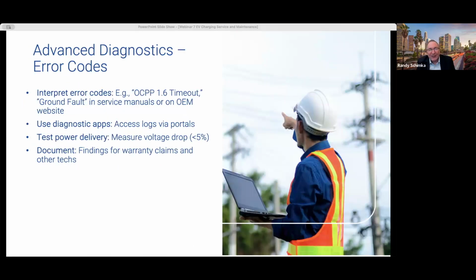So we have some advanced diagnostics for EV charger error codes that can be a little bit cryptic, like OCPP 1.6 timeout or just the generic ground fault message. So you want to check service manuals or look on the manufacturer's website for more specific meanings and fixes, so that you can quickly pinpoint exactly what the issue is. And next, you want to use any available diagnostic phone apps to access logs via the manufacturer portals to review error messages or details. This helps to make it easier to troubleshoot and resolve problems on the spot.